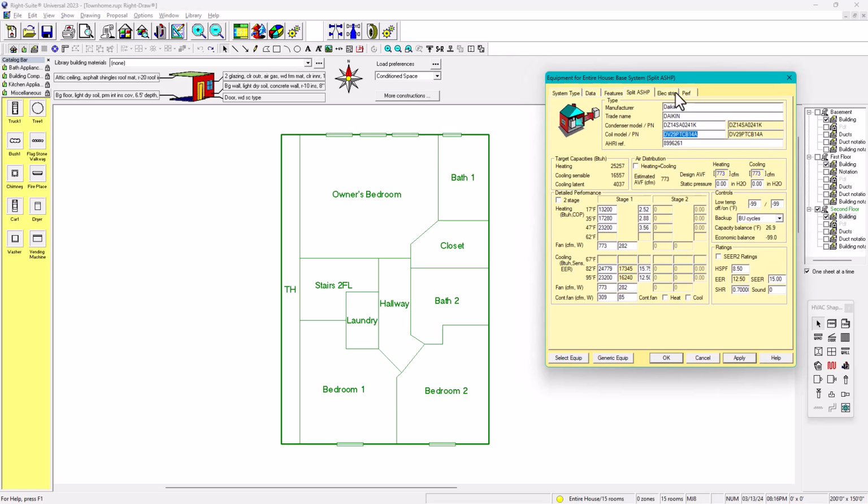Okay, so this video is becoming longer and longer. In the next video, we're gonna continue selecting this unit, because what happens is we need to check on the heating CFM. This is the heating CFM. In other videos I talk about the design CFM, target CFM, but we need to check what CFM is available based on this unit, which I'm gonna edit in the next video. And also in the next video we're going to locate where that air handling unit is located, because sometimes they show up in the first floor, second floor. We need to edit that.